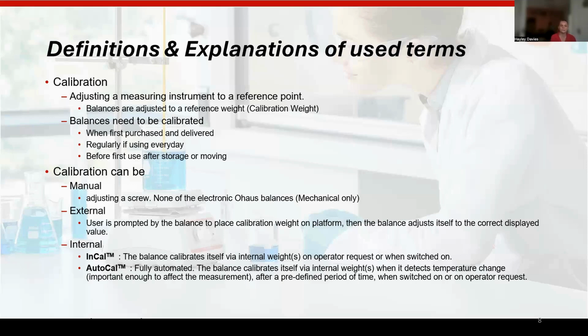And there's internal calibration. So with Ohaus, we've got InCal, which is an internal calibration. There is an internal calibration weight on the load cell inside the balance, and the balance will calibrate itself using that internal calibration weight upon operator request or when it's switched on, however you've got the balance set up to do so.